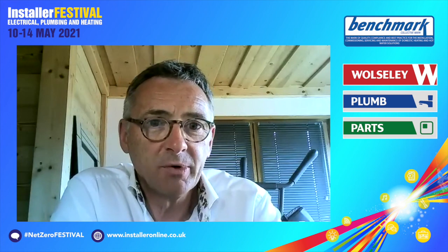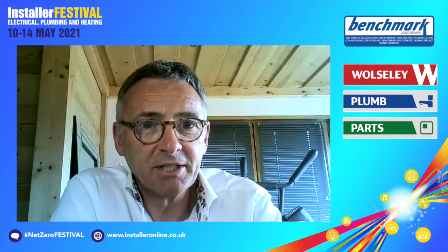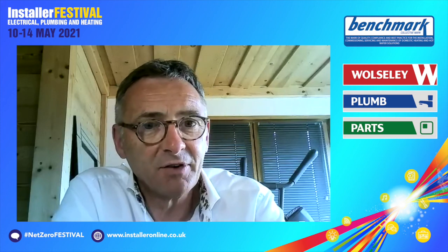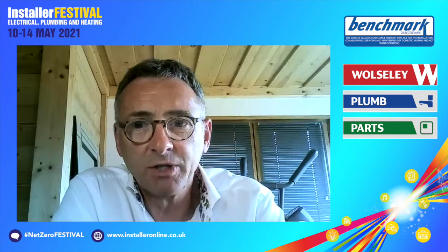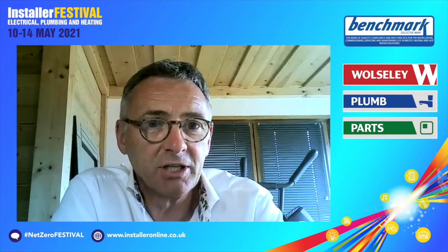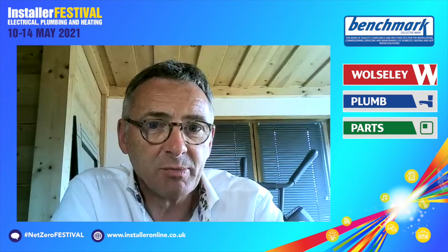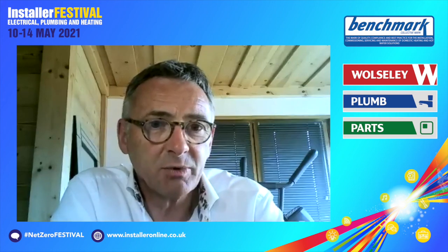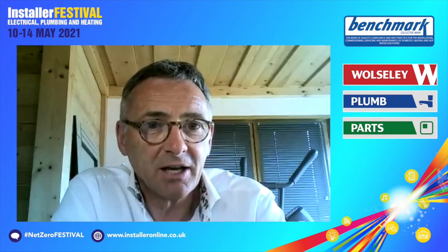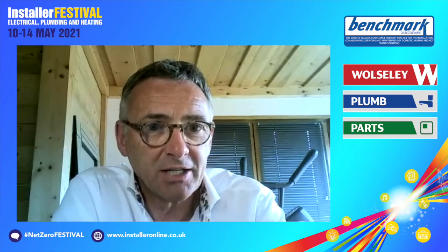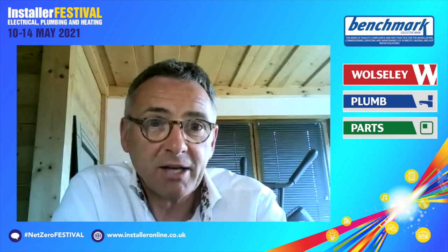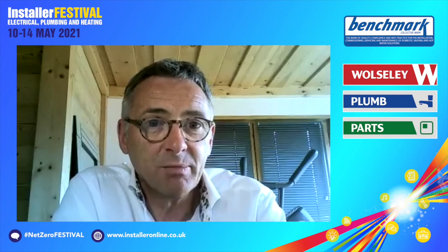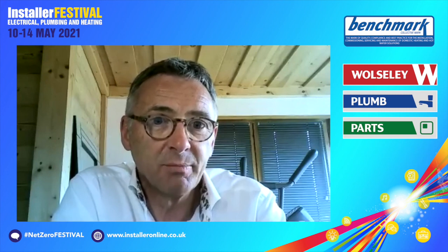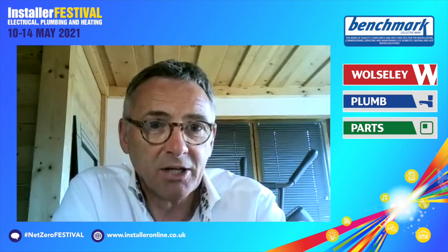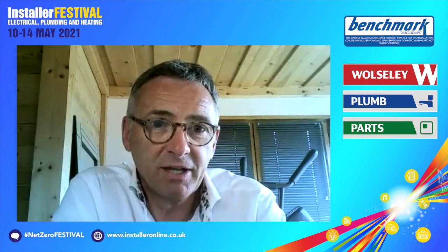There is a requirement to install your heating system following BS 7593 2019, which is the methodology applied within the benchmark app. And it also states within the building regulation that the benchmark commissioning checklist, which is the benchmark digital app, can be used for confirming compliance with building regulations regardless of the heat source used.